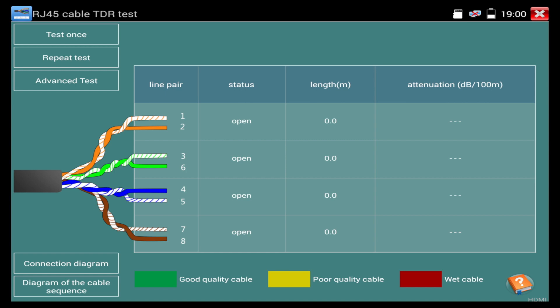Now, at this point, we're going to click the test once button. And the cable has to be over, I believe, 25 meters in order to give us the attenuation. It will tell us if it's a good quality cable, poor quality cable or a wet cable. But we can see the length in meters, it's telling us that it's an 8 meter long cable. So, it's good if you want to know the cable length.